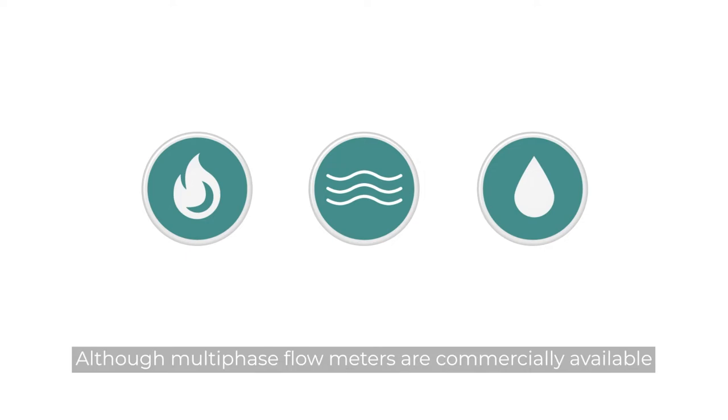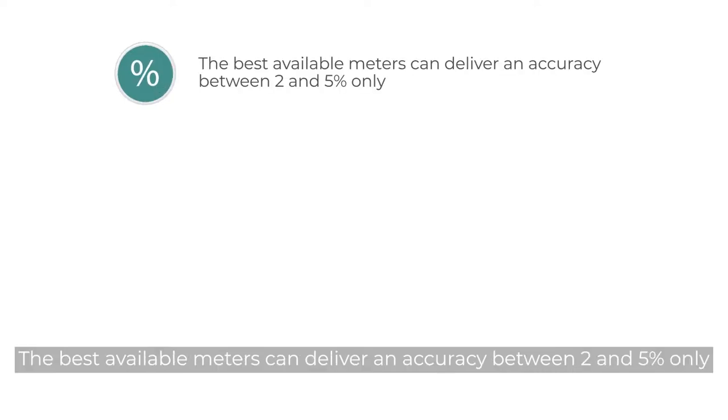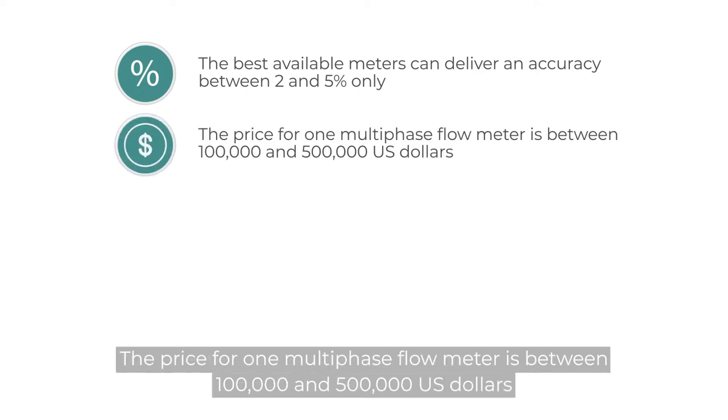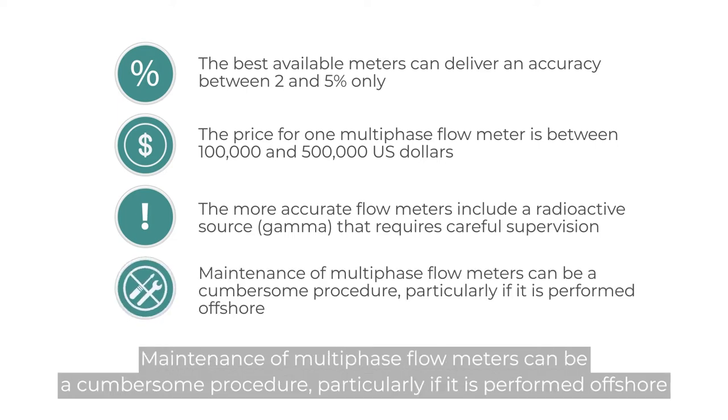Although multi-phase flow meters are commercially available, most pipelines are not equipped with them due to various reasons. For example, the best available meters can deliver an accuracy between 2% and 5% only. The price for one multi-phase flow meter is between $100,000 and $500,000. The more accurate flow meters include a radioactive gamma source that requires careful supervision. Maintenance can be cumbersome, particularly offshore.